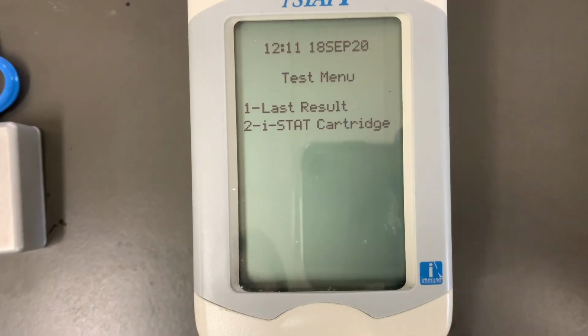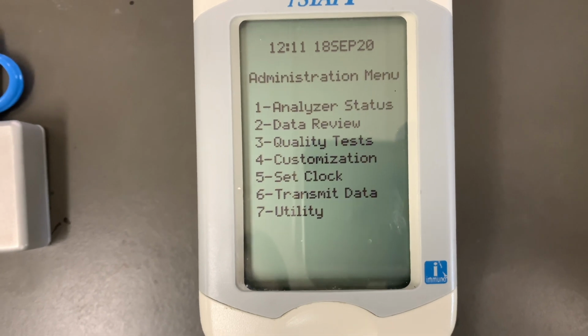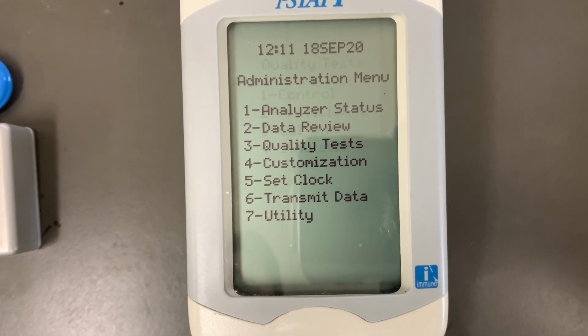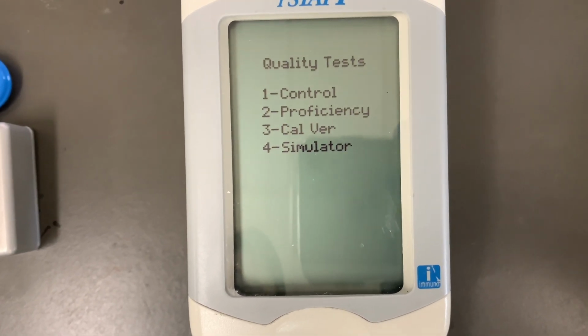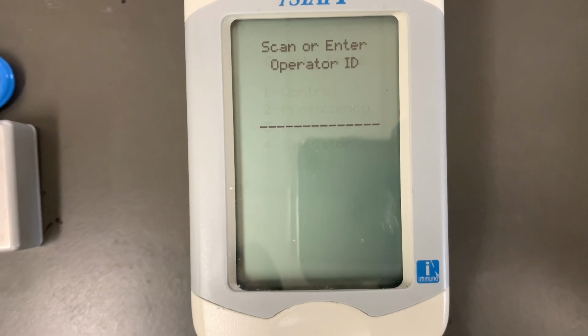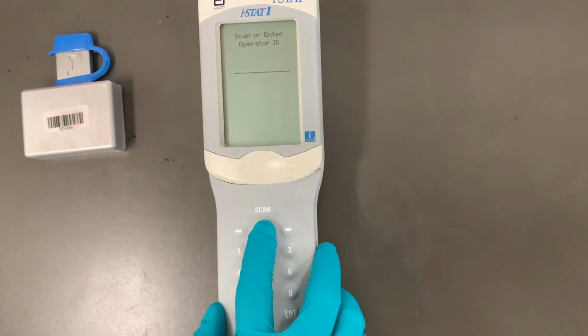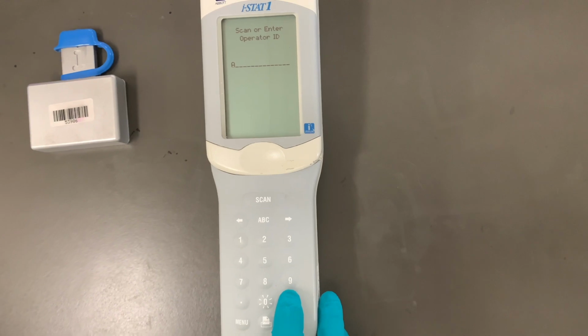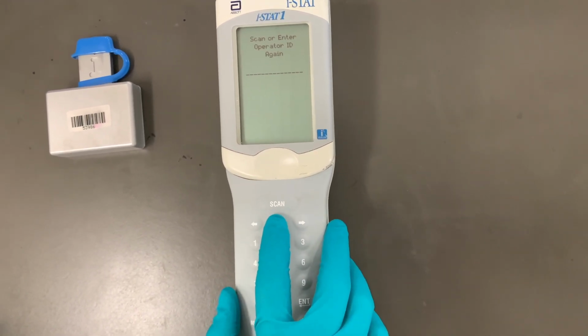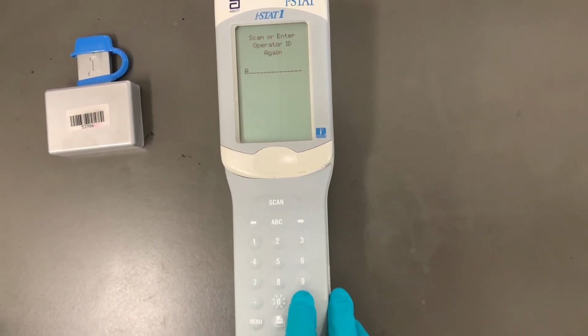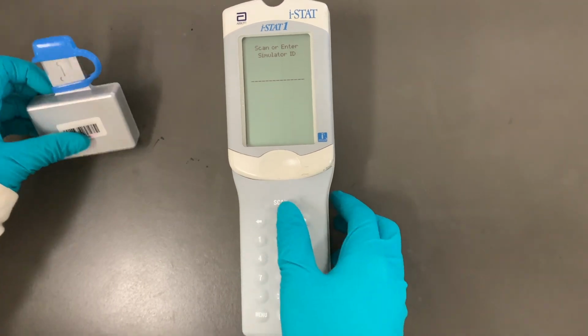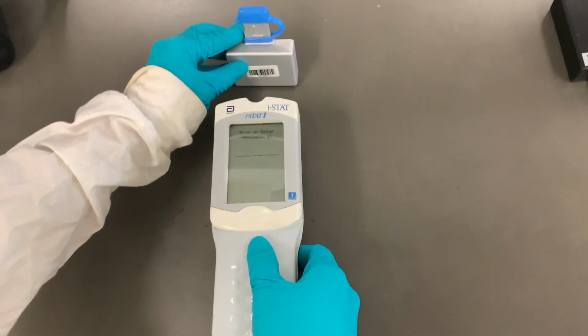To begin calibration, press the menu button and it will display an administration menu. From here, press 3 for quality test and then press 4 for simulator. At this step, you would usually enter your ID number here, but we use A as a reference. Whenever you are entering an ID number or patient number, you have to enter it twice. Now grab the simulator and scan the lot number.